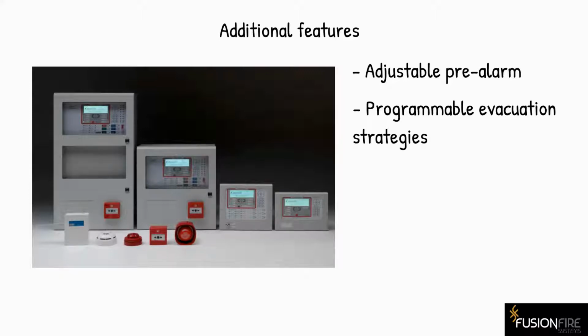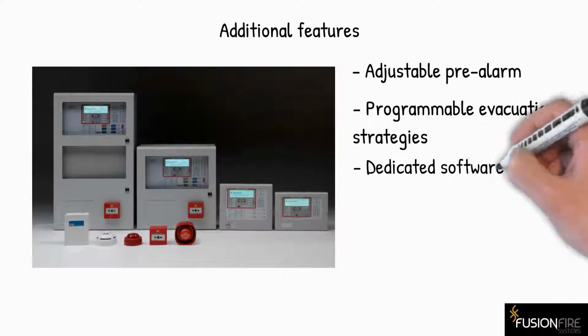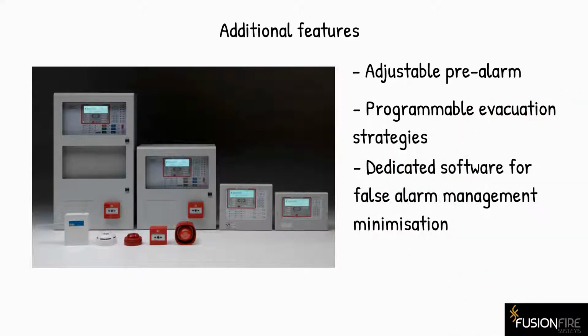The system also comes with a dedicated software called Alarm Calm to design appropriate strategies to minimize false alarms. This includes specific settings for dedicated zones or different options for different times of the day. The Axis detection system also has great features to assist installers. It has a large loop capacity with 240 addresses and 240 sub-addresses dedicated to sounder and sounder strobe bases. This reduces the cost of cabling and of hardware required, such as loop cards or motherboards.